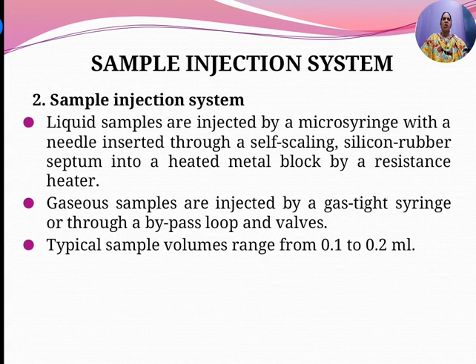Then the sample injection system. Liquid samples are injected using a micro syringe, as seen in the figure earlier. You have a micro syringe with a needle inserted through a self-sealing silicone rubber septum into a heated metal block, heated by a resistance heater. Gaseous samples are injected by a gas tight syringe or through a bypass loop and valves. Typically sample volumes range from 0.1 to 0.2 ml. Very small values of the sample are taken. So this is one of the advantages. You don't need to take a large amount of sample. The quantity of the sample is very small, 0.1 to 0.2 ml. So this is your sample injection system.